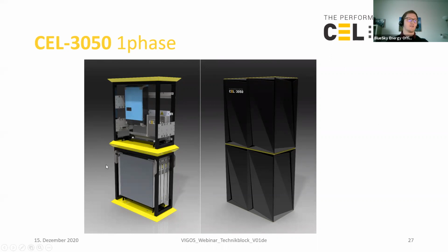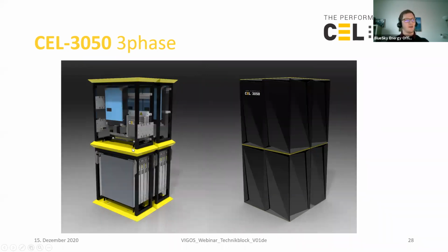Here you have the connection box, and here you have the battery modules. So this would mean this is a 10 kilowatt hour one-phase system with 4 kilowatts in power. And here, this is how a 3-phase system can look like. So you don't need to place the boxes behind each other. You can also place them in one line. So you have the second box standing on the right side of the first. And here in the bottom, you can see these 10 modules now, which gives up to 20 kilowatt hours. And here on the right side, you just see the same system, but with the added housing.